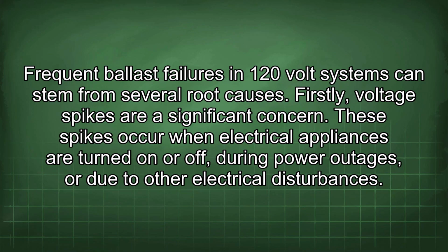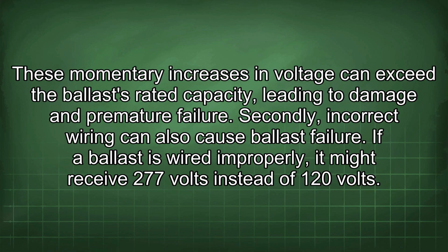Frequent ballast failures in 120-volt systems can stem from several root causes. Firstly, voltage spikes are a significant concern. These spikes occur when electrical appliances are turned on or off, during power outages, or due to other electrical disturbances. These momentary increases in voltage can exceed the ballast's rated capacity, leading to damage and premature failure.